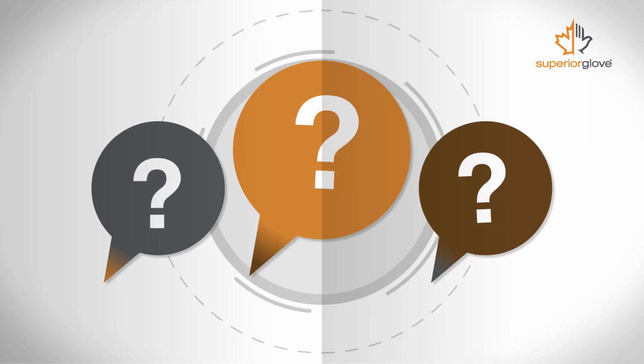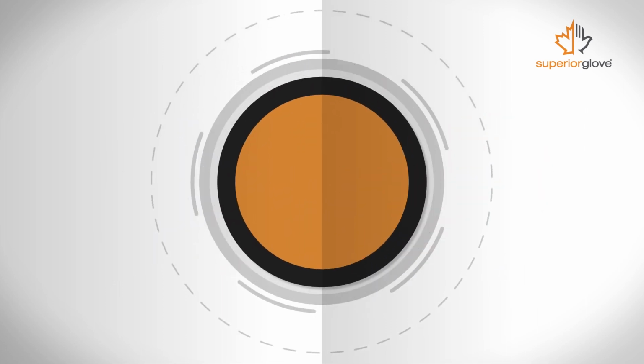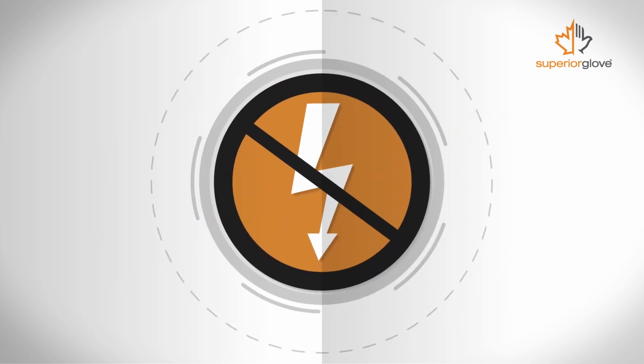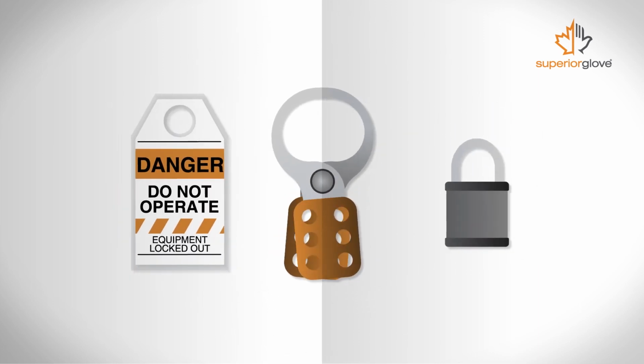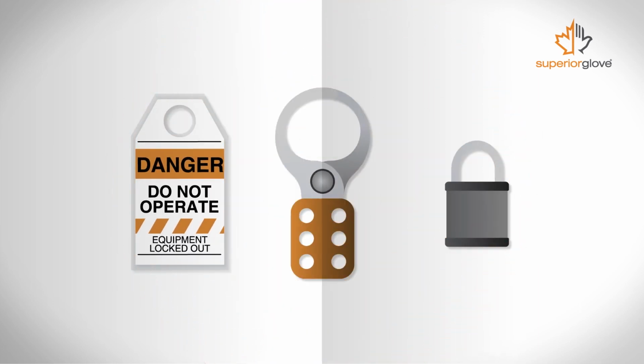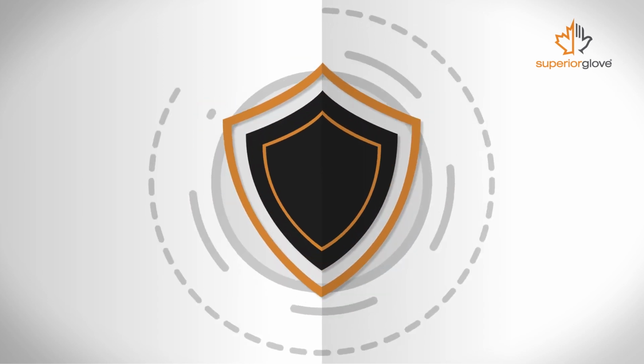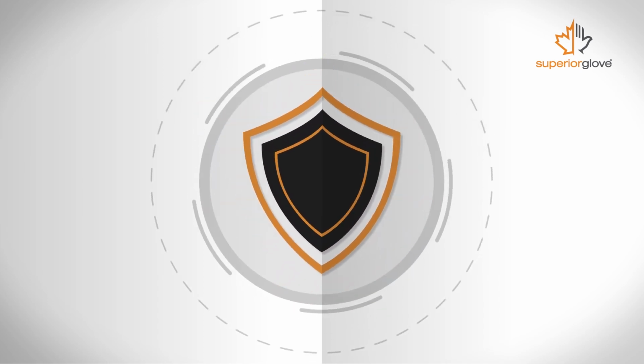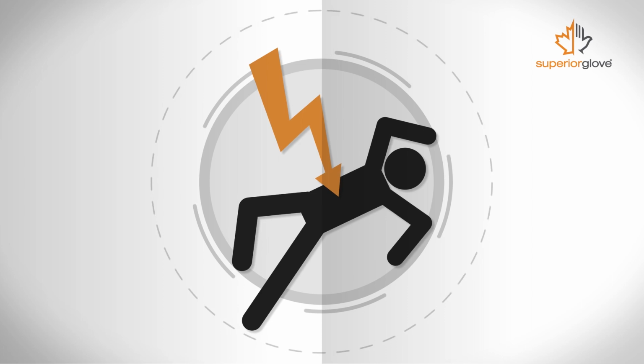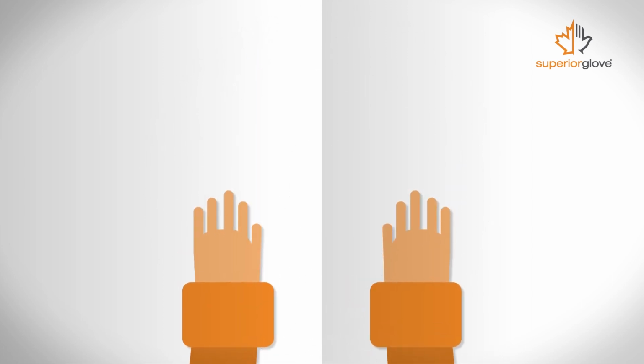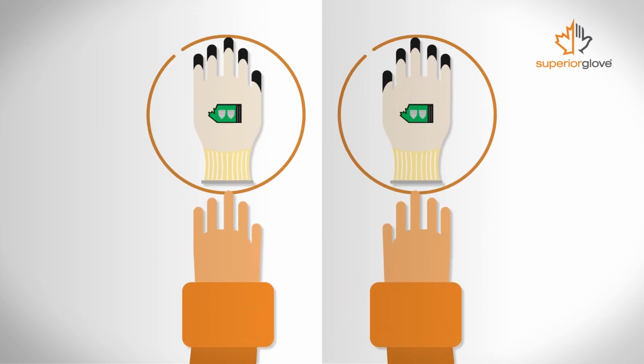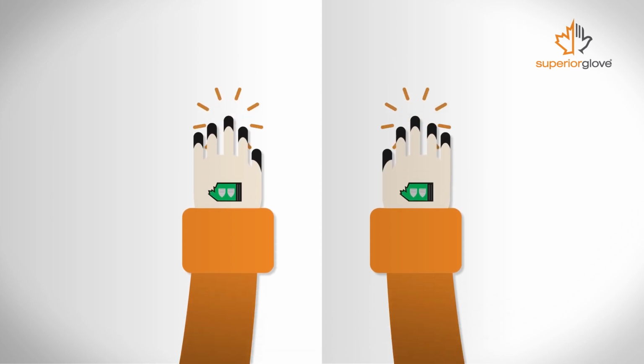The only foolproof way to eliminate the risk of an arc flash is to de-energize the equipment through lockout-tagout procedures. If you do need to work on energized equipment, you're going to need protection. Your entire body is vulnerable to an arc flash. But because we're a work glove company, we're going to look only at arc flash rated gloves. But these ratings apply for other personal protective equipment too.